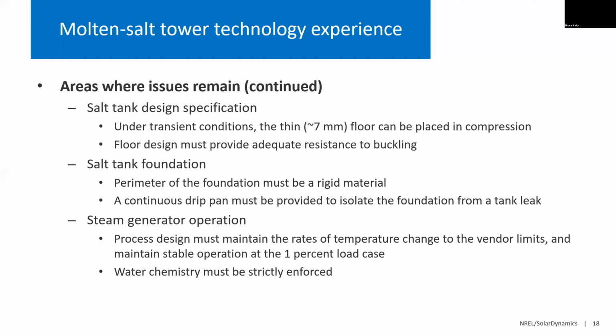Also, a drip pan needs to be provided underneath the tanks to isolate the foundation from a leak. The thermal conductivity of salt is pretty high, much higher than the foundation material would be. And so if the tank develops a leak and the foundation becomes saturated with salt, its thermal conductivity goes way up, as do the heat losses. And that winds up being a problem with tanks.